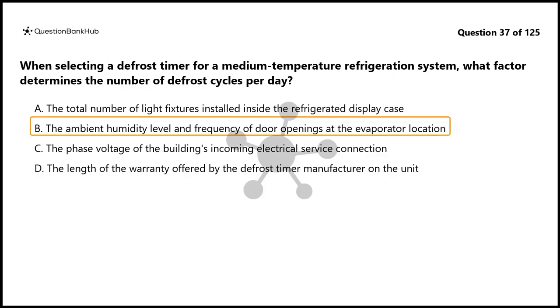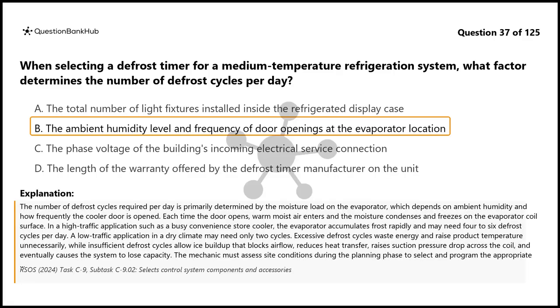The correct answer is B. The number of defrost cycles required per day is primarily determined by the moisture load on the evaporator, which depends on ambient humidity and how frequently the cooler door is opened. Each time the door opens, warm moist air enters and the moisture condenses and freezes on the evaporator coil surface. In a high-traffic application such as a busy convenience store cooler, the evaporator accumulates frost rapidly and may need 4 to 6 defrost cycles per day. A low-traffic application in a dry climate may need only 2 cycles.